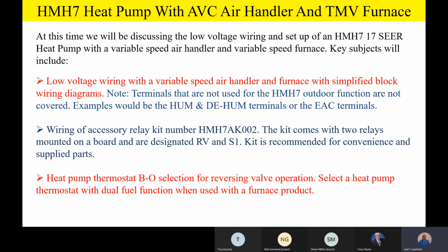Now, it should be noted, please write this down or put this in your hip pocket: on any variable speed product, one more time, on any variable speed product, you're going to have to use that wiring accessory kit 002, that HMH7AK 002 kit, because it has 2 relays on it, and they're going to be mounted on the board, and they're going to be designated RV and S1. And that 2 relay kit has to be used on variable speed. Now, we're going to recommend the kit again for convenience and supplied parts.